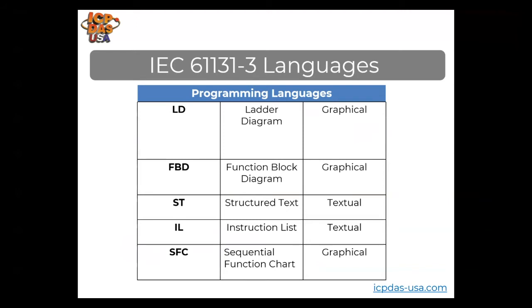IEC 61131 is the only internationally recognized industrial automation control language to support all 5 PLC languages, including ladder diagram, function block diagram, structured text, instruction list, and sequential function chart. Ladder diagram, function block diagram, and sequential function chart are graphical, while structured text and instruction list are textual.